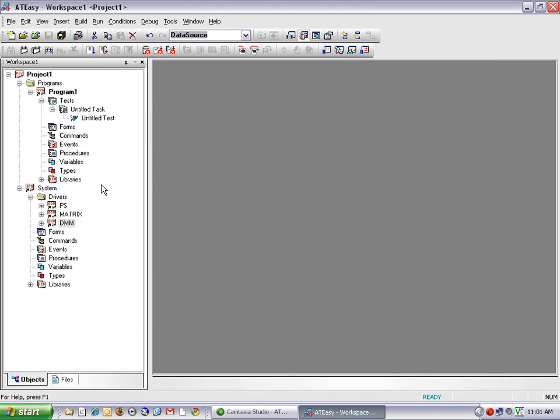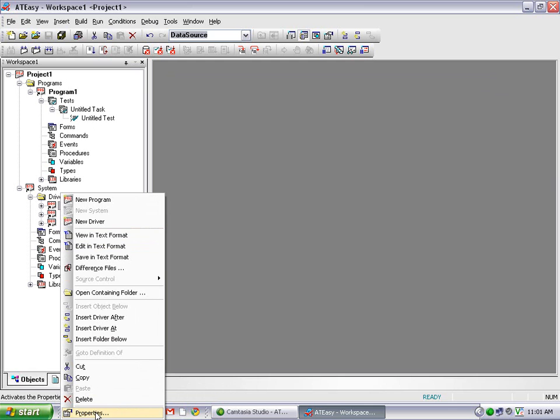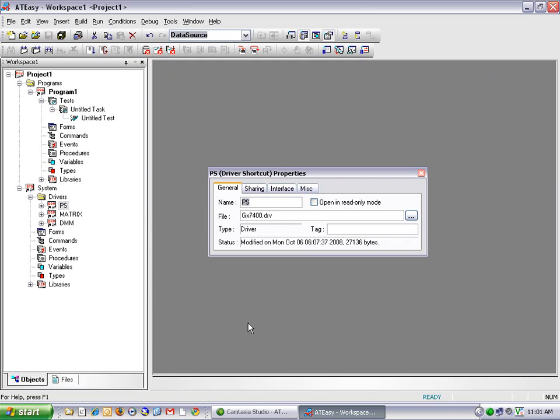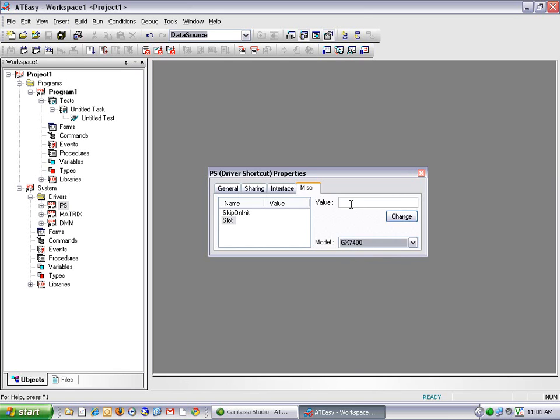So I'll start with the power supply. I can right-click on the power supply driver shortcut and select Properties. Now I'll get the Properties dialog box, and I can click the Miscellaneous tab and configure the slot number. Now in this example, the power supply is a GX7400, which is a PXI instrument. So it's addressed using slot numbers. I'll assign this instrument slot number 2.